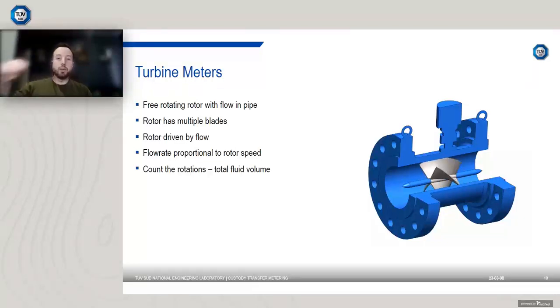So typically there's a magnetic pickup. Every time a blade passes the pickup, a pulse is generated. And what you do is you count the number of pulses, and that tells you the total volume that's passed through the meter if you use it with a K factor or a meter factor.